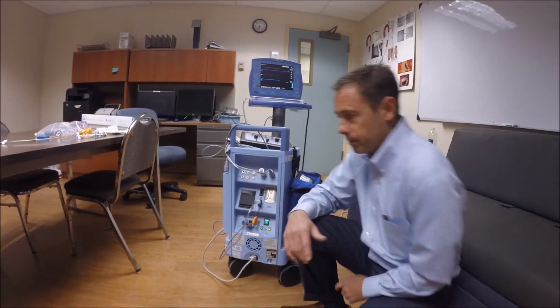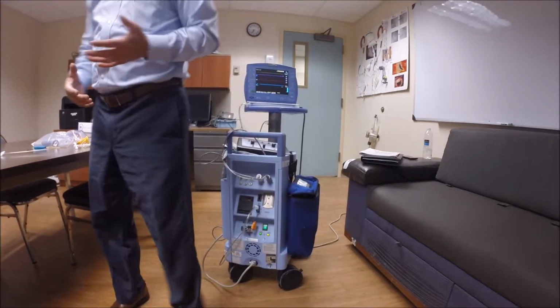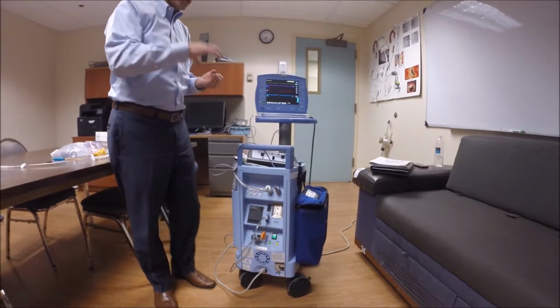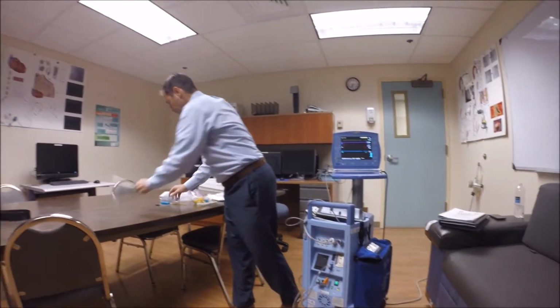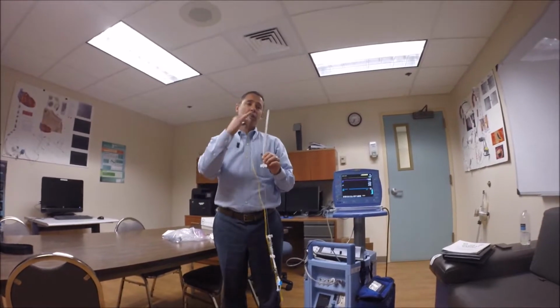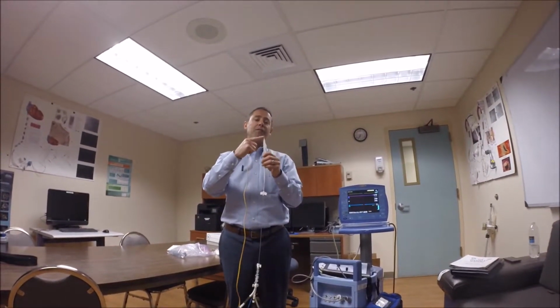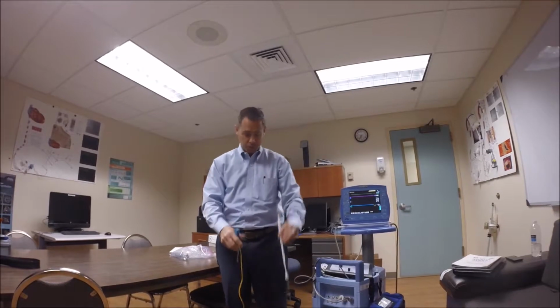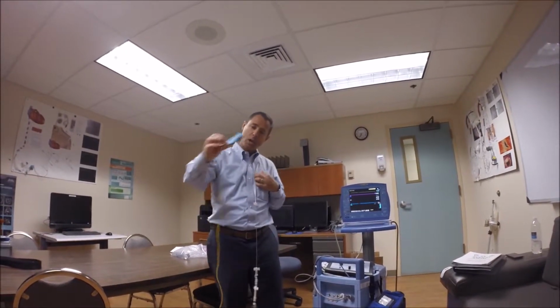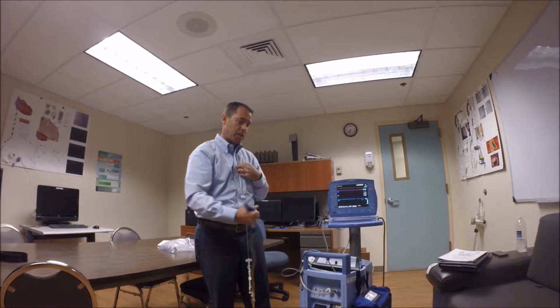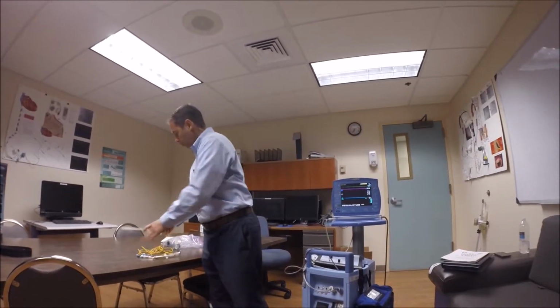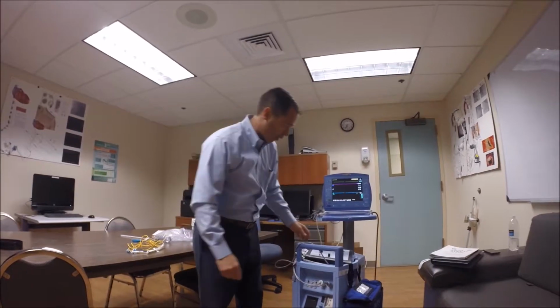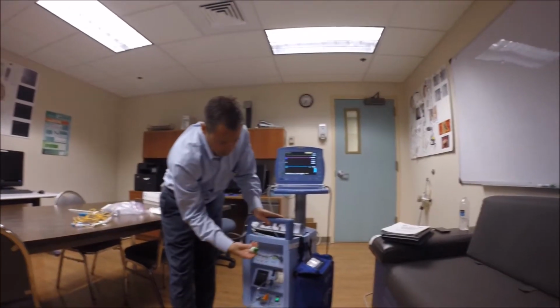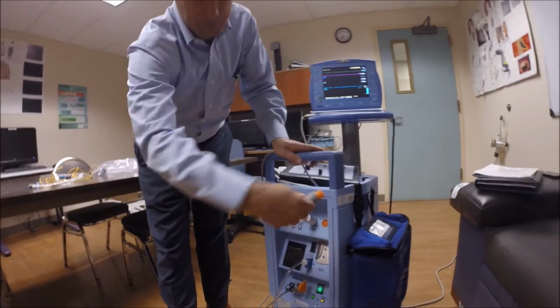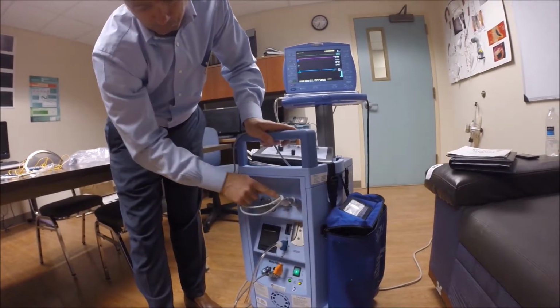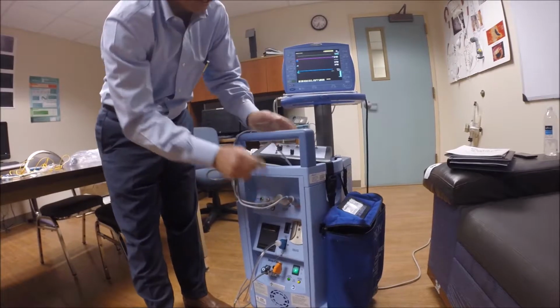In a STEMI, you don't necessarily have to have your ECG connected or your transducer connected. You can utilize the fiber optic catheter. This sensor at the tip is a high-fidelity AP signal. So for STEMI patients, you get the catheter in the patient, we've handed off the fiber optic that's connected, and you're off and running. However, for regular patients, we want to make sure that we have our patient connections. Here's my ECG connection here. Here's my transducer connection here. Green for ECG and orange for your AP.